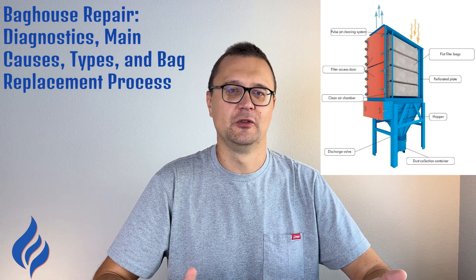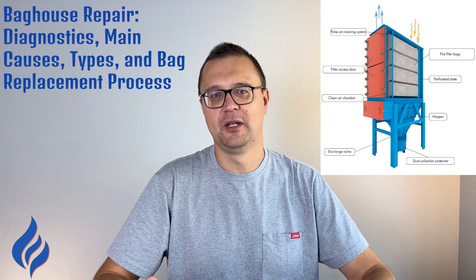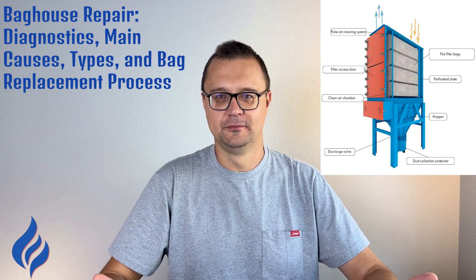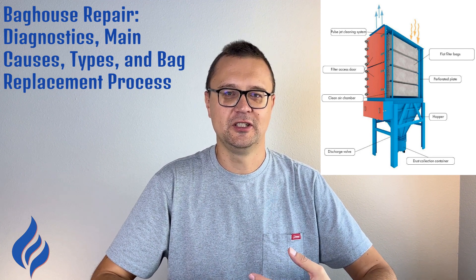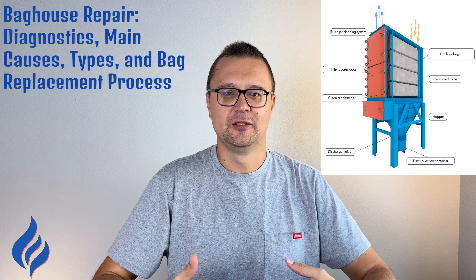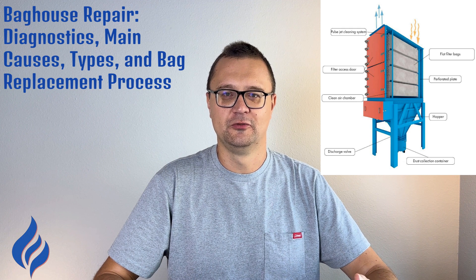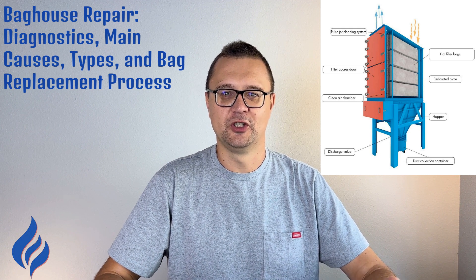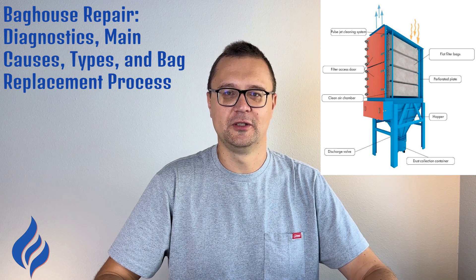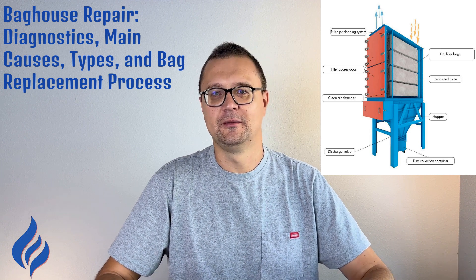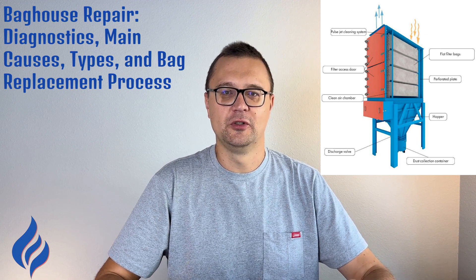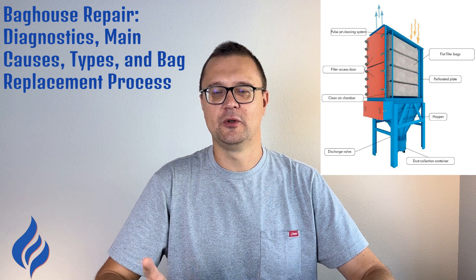Main Causes of Bag House Repair. Let's break down the main reasons why bag houses end up needing repairs. Incorrect Equipment Selection. One of the most common causes of poor bag house performance is simply that the wrong equipment was chosen for the job. If the filtration area is too small or the dust load is too high, the system can't perform effectively. Unfortunately, this problem often arises because customers try to reduce capital costs, only to face expensive repairs later on.